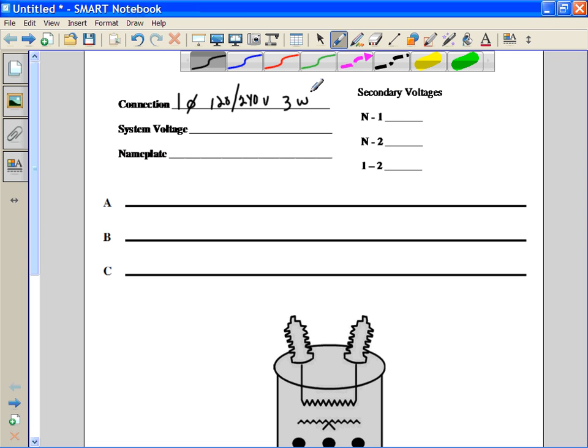And we'll connect this to a Y primary circuit again, and let's just use an example of a 2400 4160 Y circuit in this instance. So again, we need to go out to the transformer yard and find the transformer that will work on this particular application. We need a transformer that we can connect to this primary system, and that transformer is going to have a rating on its nameplate that will read 2400 4160 for the primary voltage, and 120 slash 240 volts for the secondary.